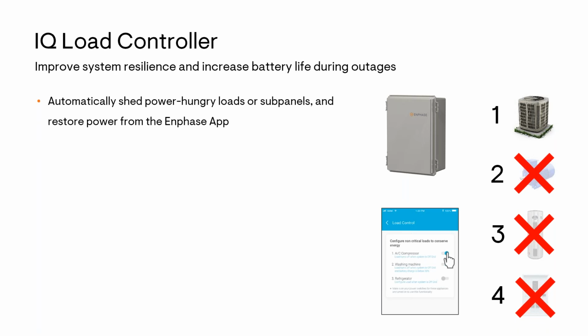Now this feature is fairly configurable as well. For example, the behavior can be customized for each individual load differently. One load could be set to turn on or off depending on the battery's state of charge. This might be done to prevent large loads from totally draining the battery. Or loads can also be set to only have power if there's an integrated generator and it's operating in parallel with the solar. Therefore, you would have that extra power from the generator.